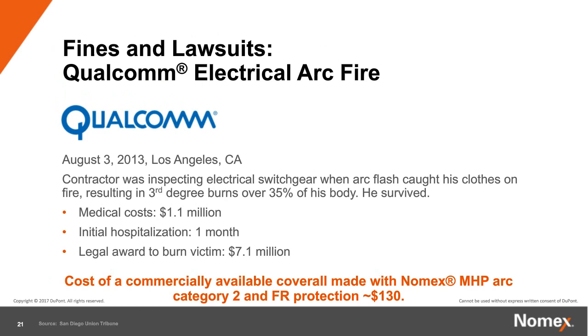Let's look at an accident with an electrical source that resulted in an arc flash and fire. In August of 2013, an outside contractor was working at a Qualcomm facility in Los Angeles. There was a miscommunication about lockout-tagout, and the contractor removed the protective cover from a live 4,160-volt circuit breaker. He was holding a metal measuring tape in his hands at the time. An arc flash occurred, setting the victim on fire, resulting in a 35% total body surface area burn.